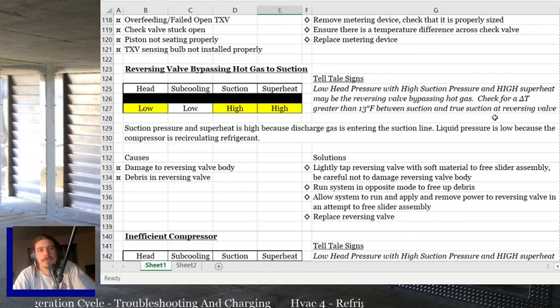If you are working on a heat pump, the first thing you want to rule out is an issue with the reversing valve. So low head pressure with high suction pressure and high superheat may be the reversing valve bypassing hot gas. Check for a delta T greater than 13 degrees between the suction at the reversing valve and the true suction going to the compressor. 13 degrees. It's a big temperature difference, but you've got discharge gas commingling right next to suction gas right at that reversing valve. So that suction line is going to pick up heat, doesn't matter what you do. But if you're picking up more than 13 degrees going across that reversing valve, then it's bypassing hot gas. So it's a pretty high temp.